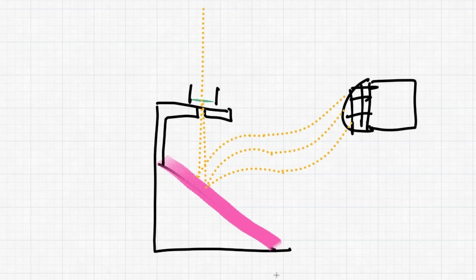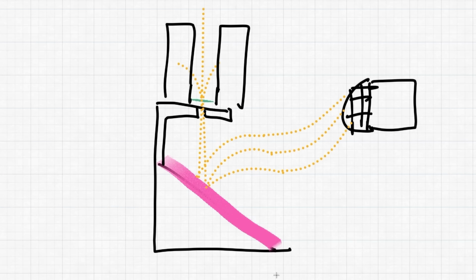And we've effectively created a transmission electron microscope inside the chamber, because what we're seeing are electrons that have passed through the sample and then are picked up by the secondary detector. Whereas any of the electrons that might bounce off the sample, we're ignoring because we're not using the backscatter detector. And any secondary electrons that come off the sample and float around at the top are being collected by a special sleeve that absorbs them.